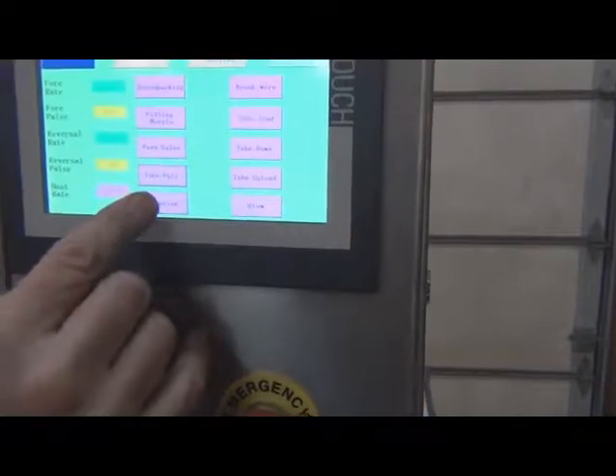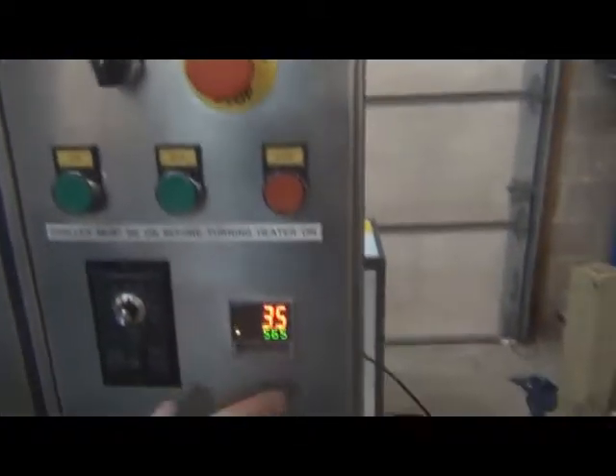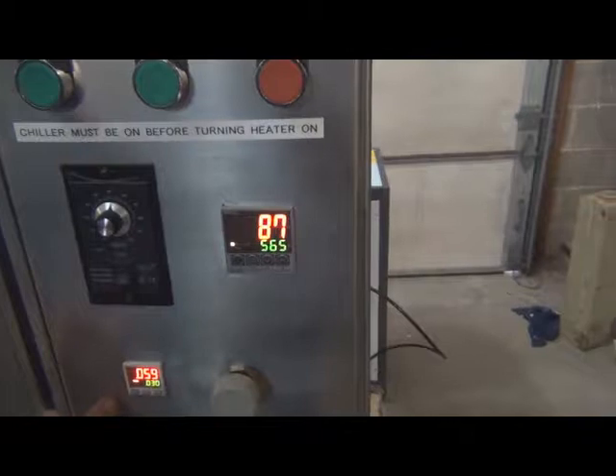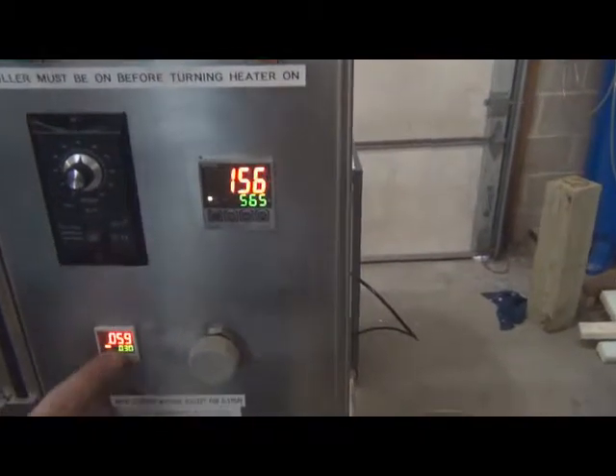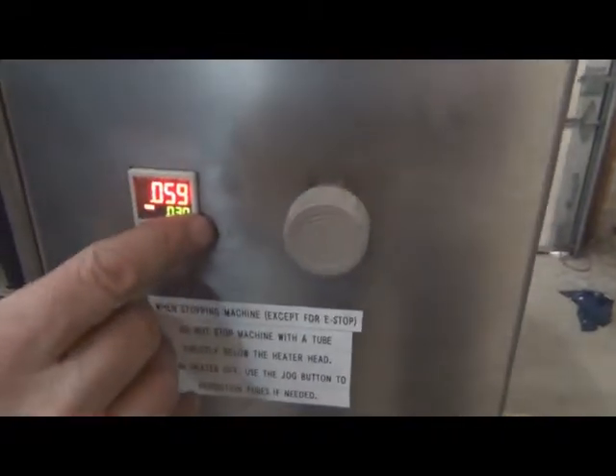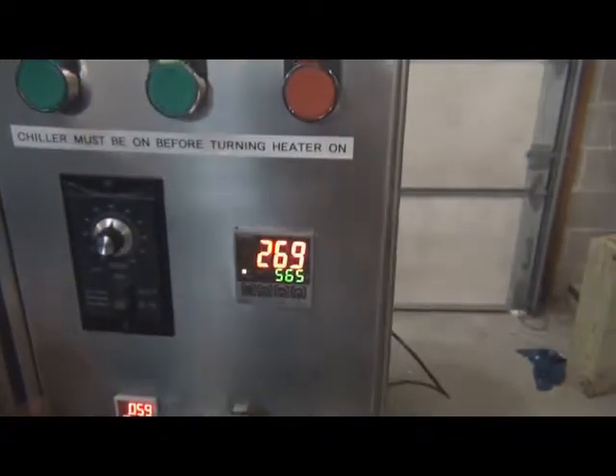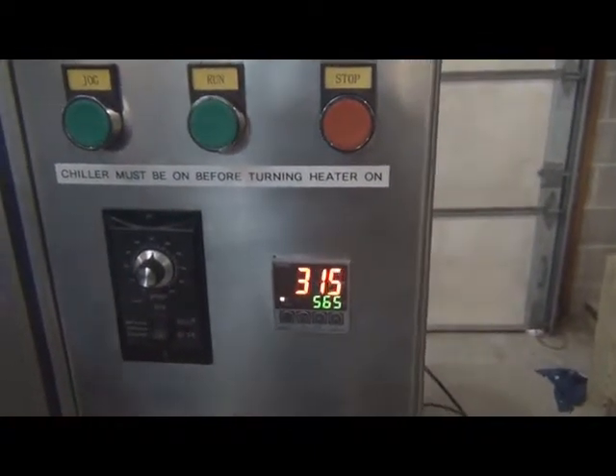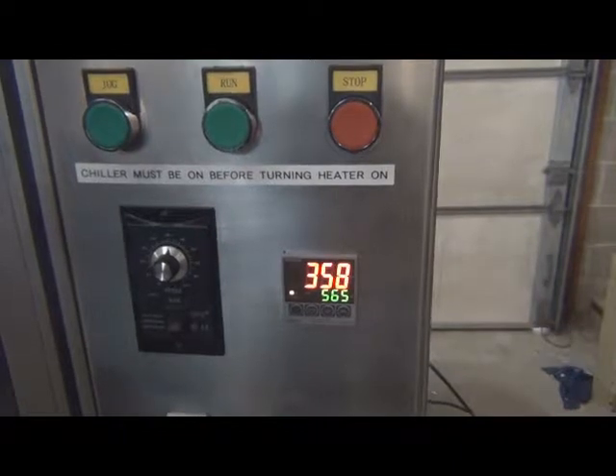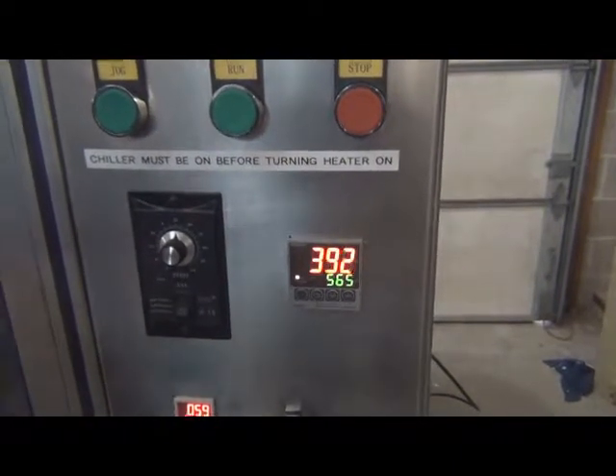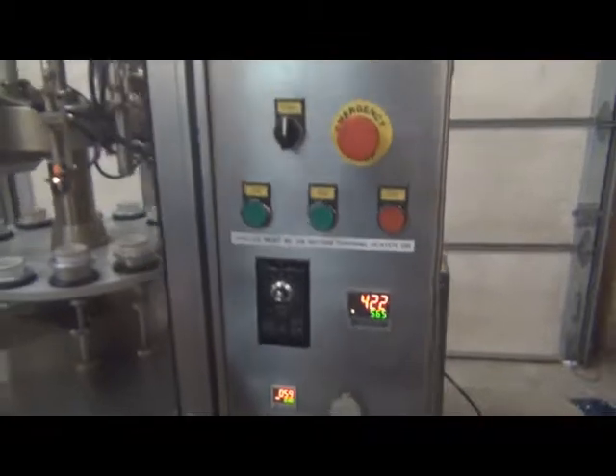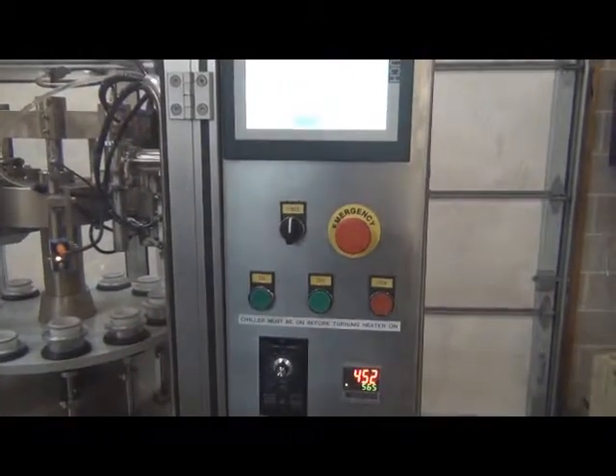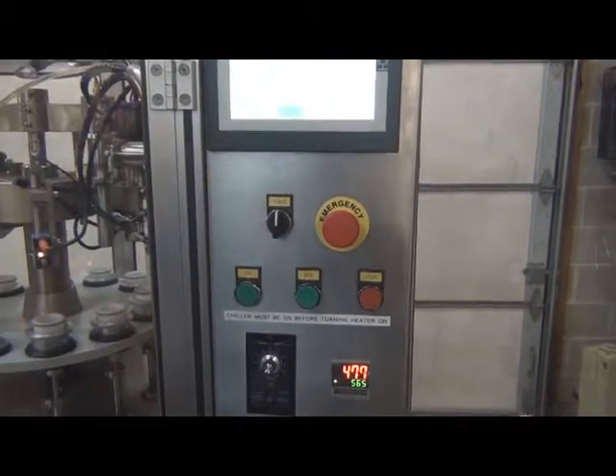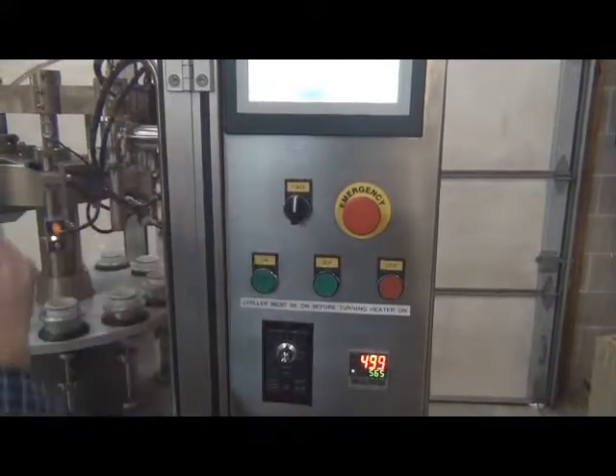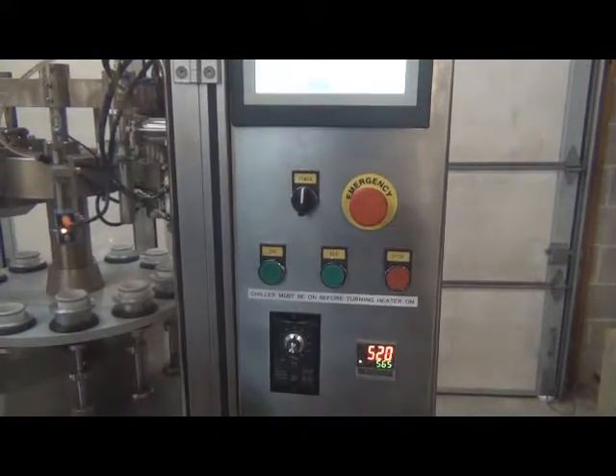Heating will start the heater even in the manual mode. You'll see it climbing now. That is as long as you have air, as long as you have more than 30 units of air. Now, as I mentioned, the heater does know that it has air, but it doesn't know that the chiller's on. That's why the first thing I did when I started the machine up was turn the chiller on, because the heater doesn't know, and it'll get too hot for those fittings if there's not water running through there. So that's that.